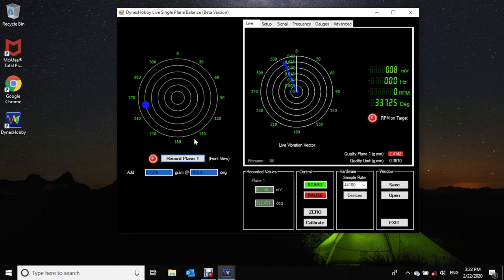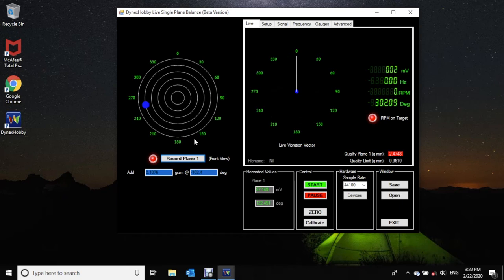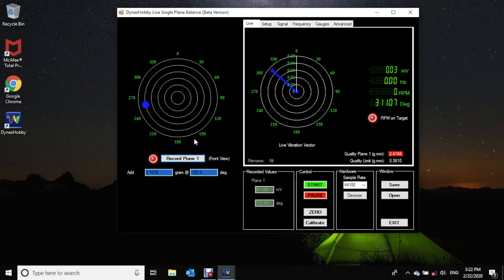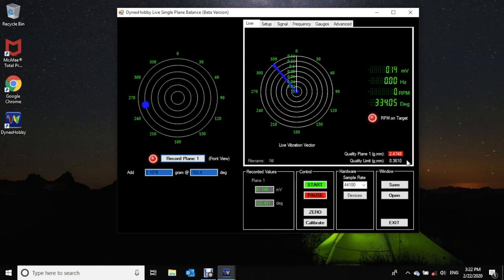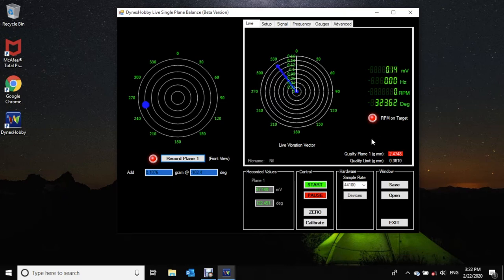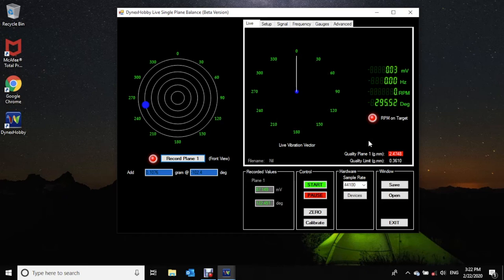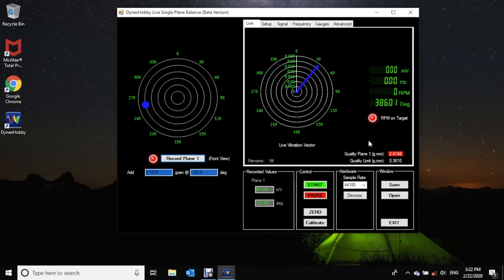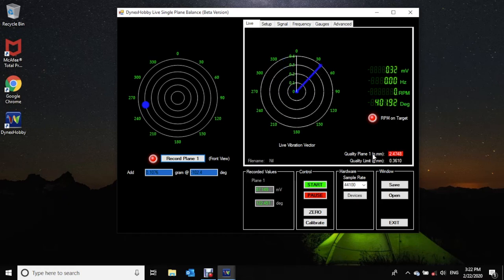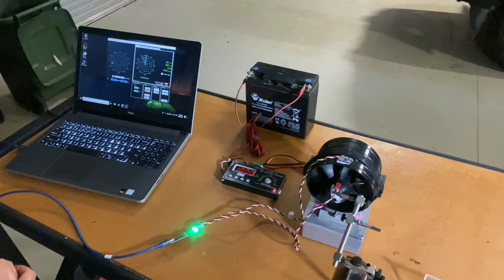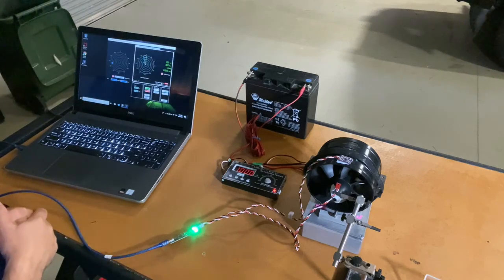Now, if you look on the quality plane, what you'll see is that the system is set up to balance to a quality limit of, say, 0.361 gram millimeters, which is quite fine, actually. So with our current EDF in its current state, it has a quality limit of about 2.47, which is quite high. So essentially our EDF is imbalanced, and we need to bring that back to an acceptable level.